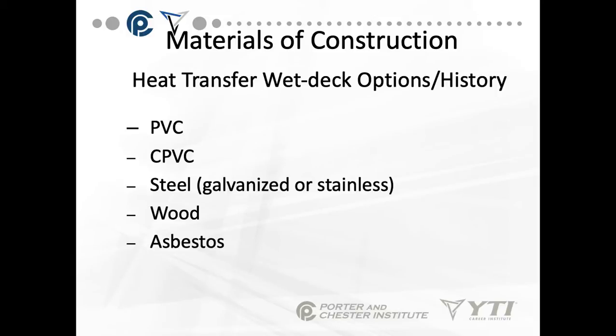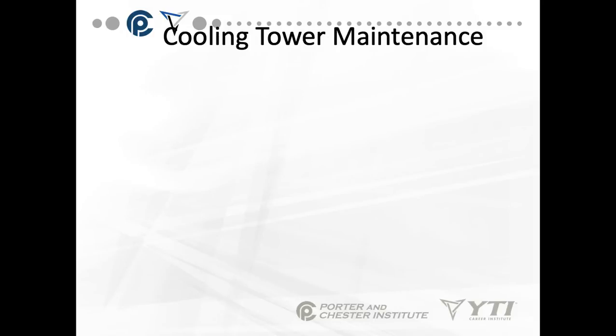So, the materials that the wet deck, that's the area where the water flows down and evaporates from, is either made of PVC, CPVC, or steel, but it would be galvanized or stainless. We don't want it to rust. Wood or asbestos. Asbestos isn't used that often anymore because of the health concerns.